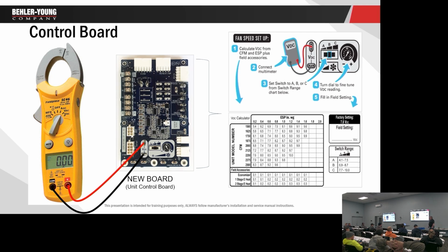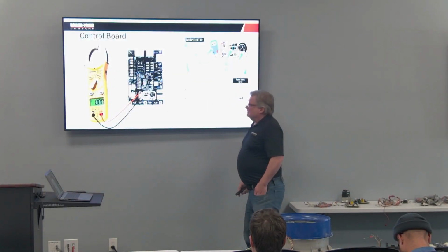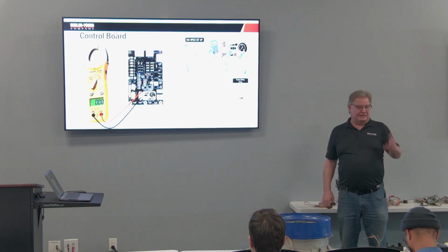Okay, so 2 is kind of the limit. You can get slightly beyond it, and so you can get some high static systems, but I'm talking about your typical rooftop unit. So, coming back to this thing here, we have 2,000 CFM. We figured we had 1 inch of static, right? I had 0.4 in the return, 0.5 in the supply, add them together, I got 0.9.